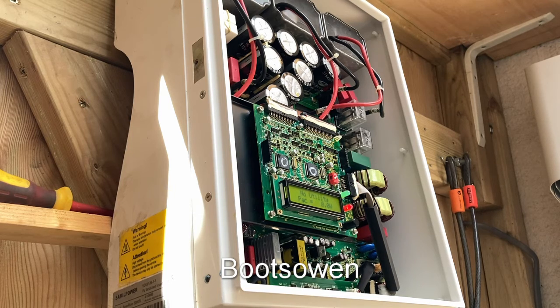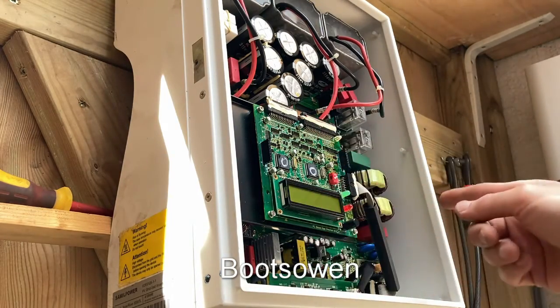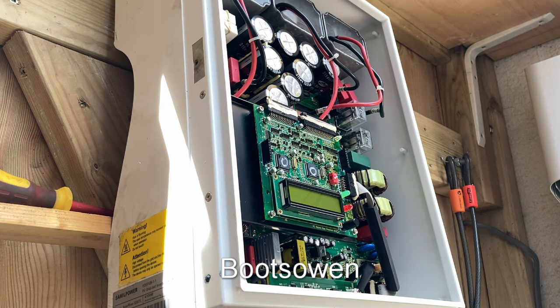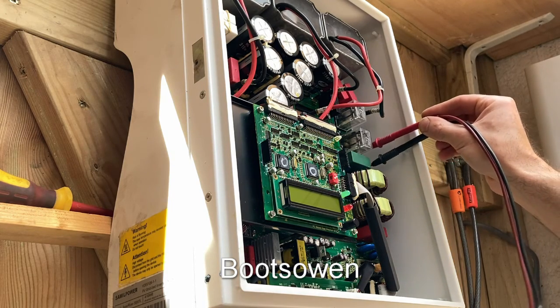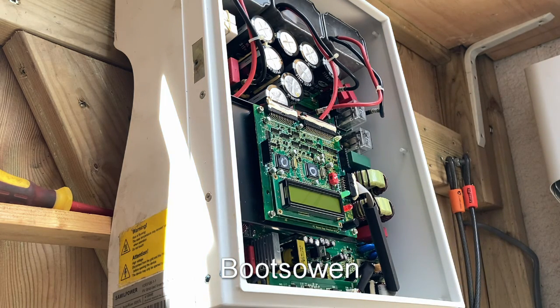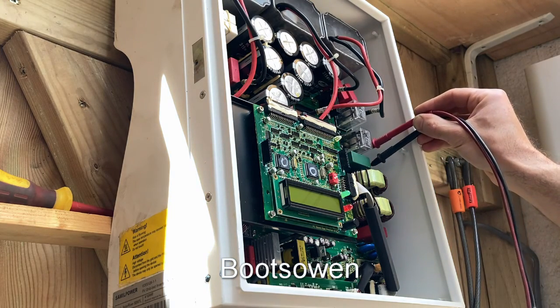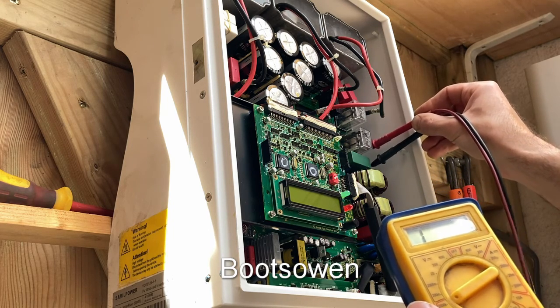Let's plug that out and switch off the DC, so now it is isolated. It looks to me like there's a DC side and an AC side — DC side here because this is where the cables are, and AC side over here. So I've got the multimeter set to resistance. There's a fuse in here — I'm not getting anything there. A fuse that doesn't have any continuity is normally a sign.